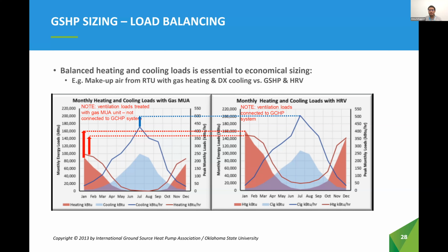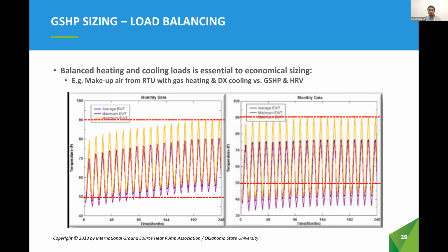While this represents a substantial increase in both the peak load and cumulative energy, it also results in a better overall balance between heating and cooling. As a result, the heating energy is now 40% larger, while the peak cooling load is 35% larger than for heating. We can see the implications of this by looking at the ground heat exchanger itself. In fact, the size of the ground heat exchanger can actually be reduced by 8% because of this better load balance.